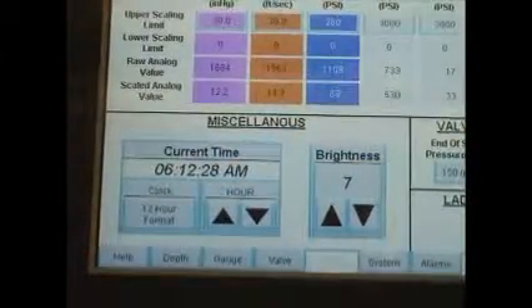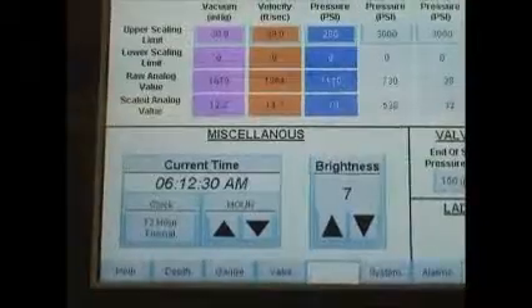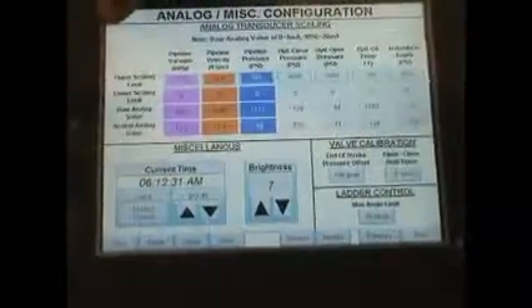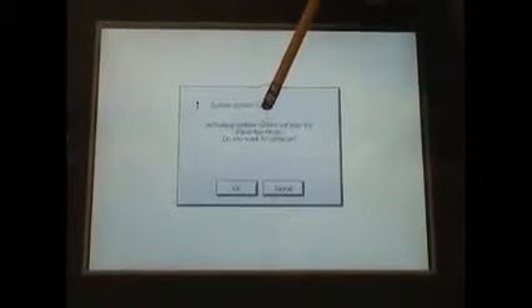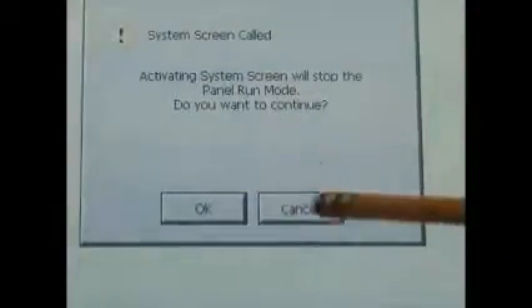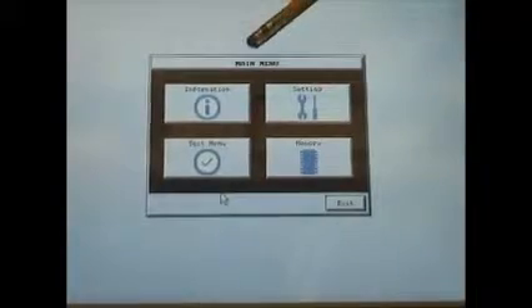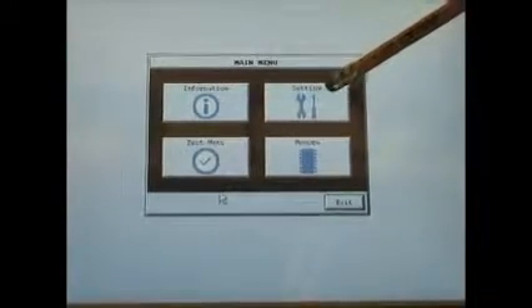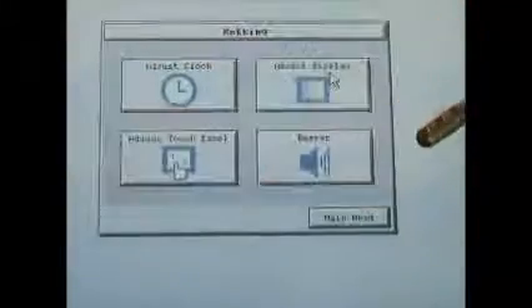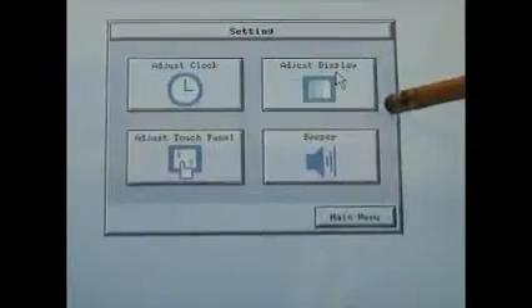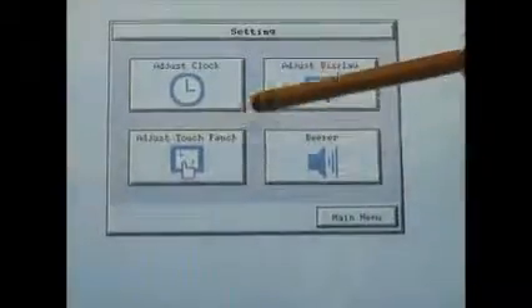To do that, you simply need to press and hold on the upper right hand corner of the screen. You're going to get a message that says activating system screen will stop the panel run mode. Simply hit the OK button. We're going to then go into our main menu, which is our settings. Touch the settings. And here we can adjust the clock right here by touching this button.